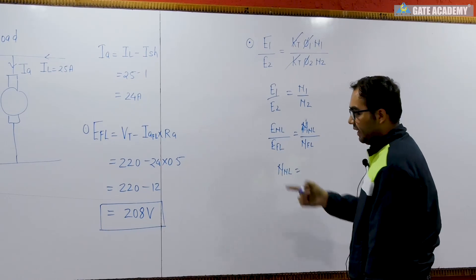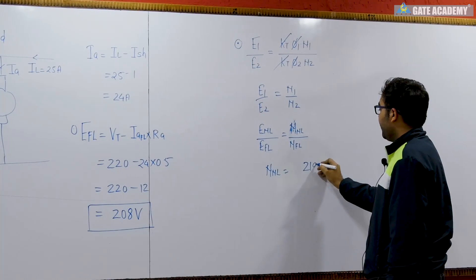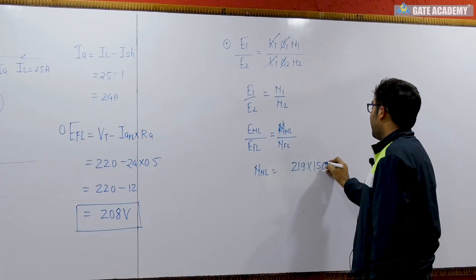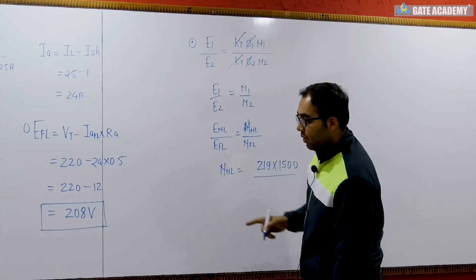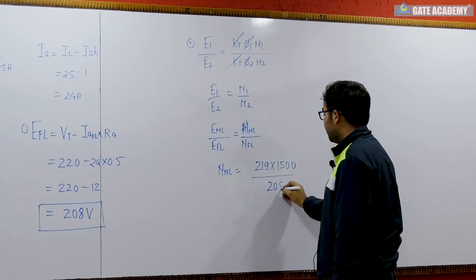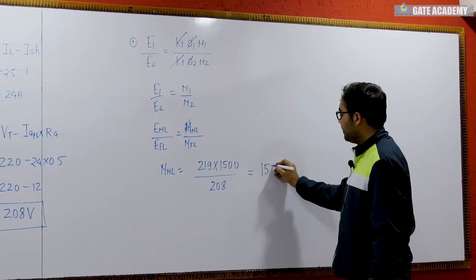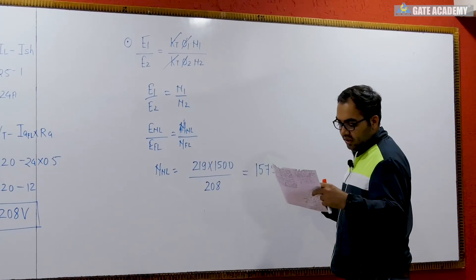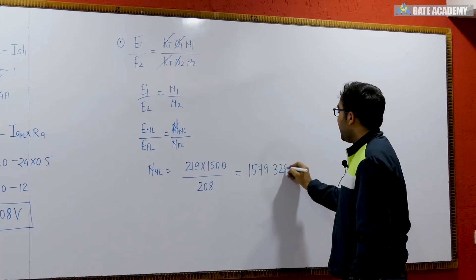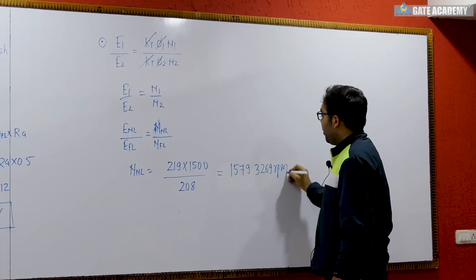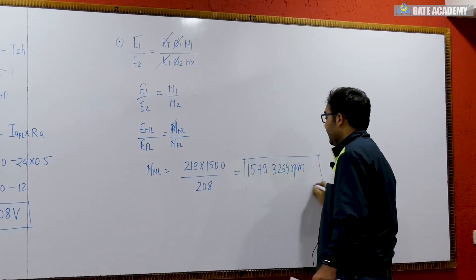So no load speed will be equal to ENL 219, full load speed is 1500 rpm, full load voltage is 208. So after solving, we are getting around 1579.3269 rpm. This is the speed of the motor under no load condition.